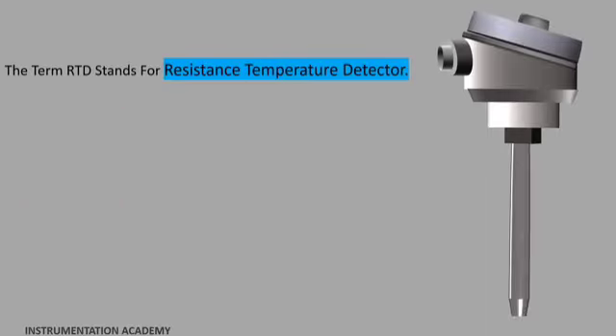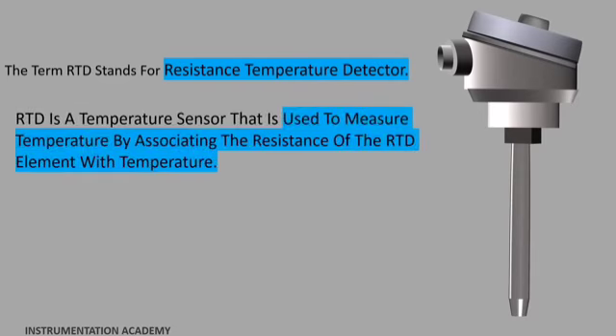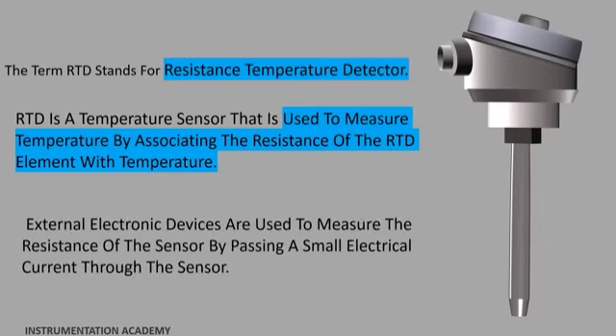The term RTD stands for Resistance Temperature Detector. RTD is a temperature sensor that is used to measure temperature by associating the resistance of the RTD element with temperature. An RTD is a passive device. External electronic devices are used to measure the resistance of the sensor by passing a small electrical current through the sensor.